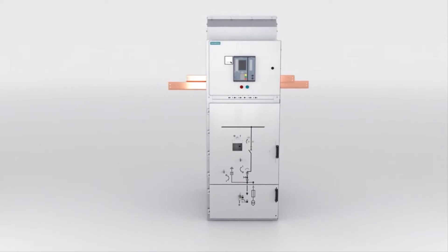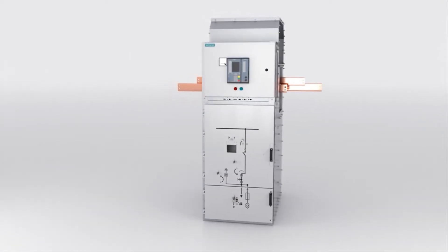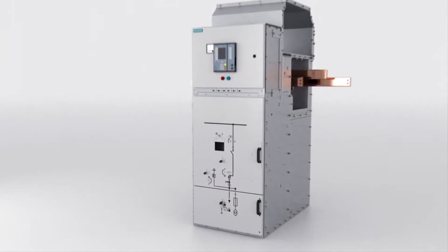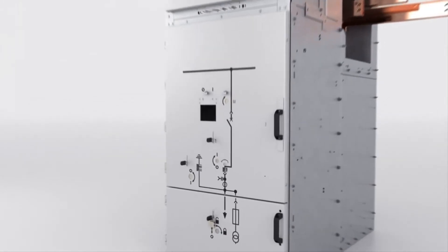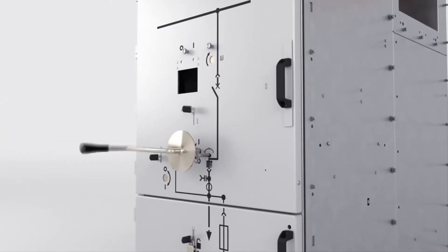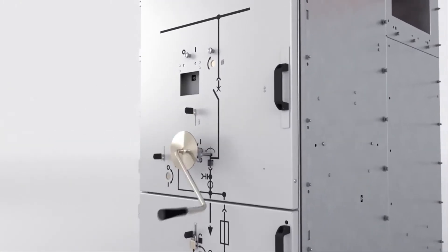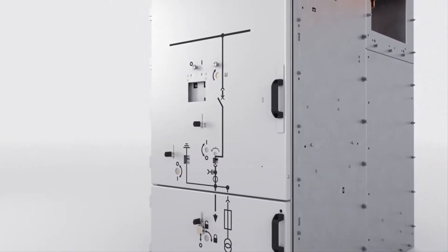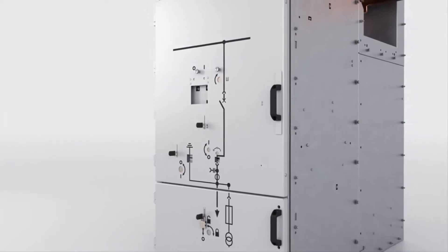Before repairing the damaged cable, the tripped circuit breaker is racked into the disconnected position. Mechanical interlocking means that the cable can only be earthed afterwards.